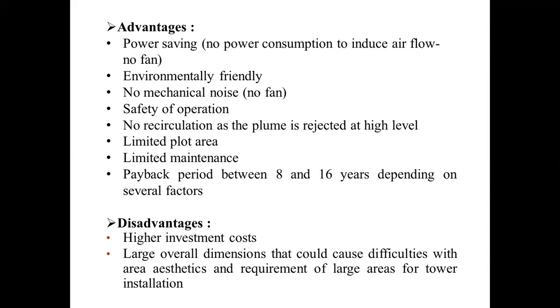Advantages of using a natural draft tower: almost no power consumption to induce airflow, no fan required, so there is a saving in power. It is environmentally friendly, with no mechanical noise as there is no fan. There is safety of operations, no recirculation as the plume is rejected at high level. Limited plot area is required. Limited maintenance. Payback period between 8 and 16 years depending on a few factors.